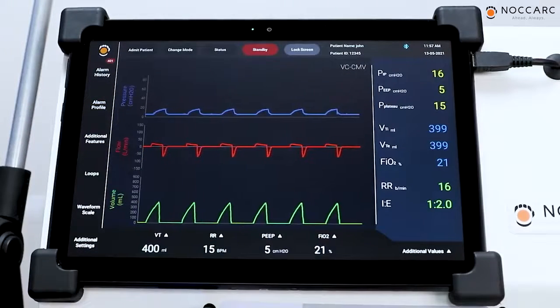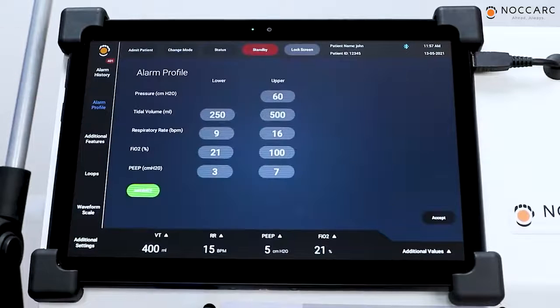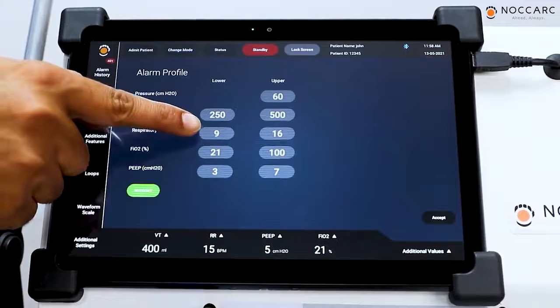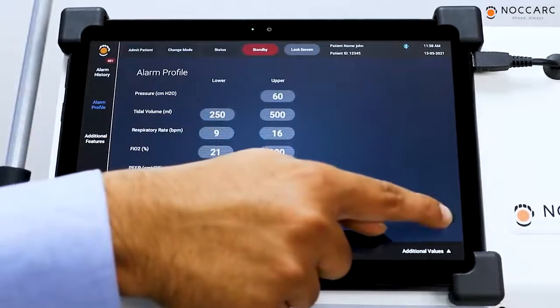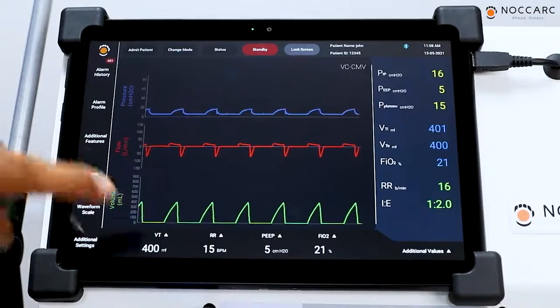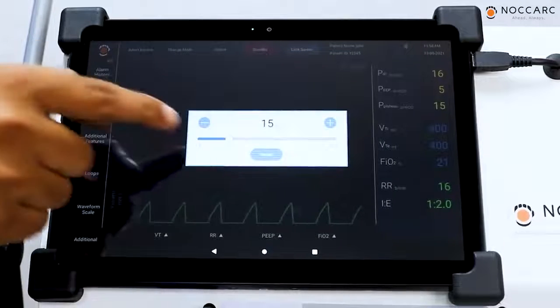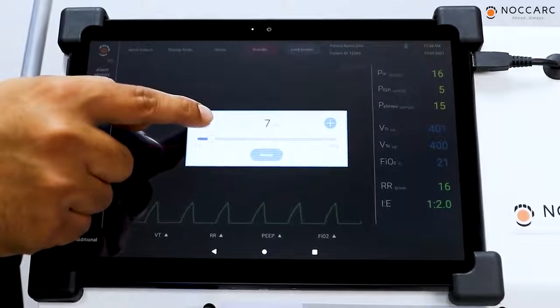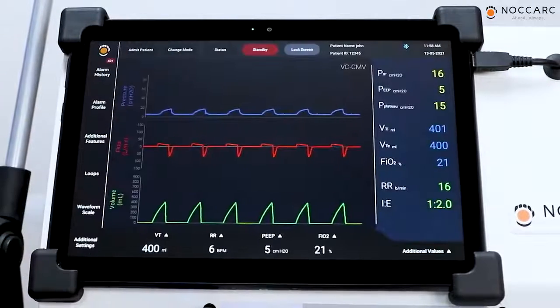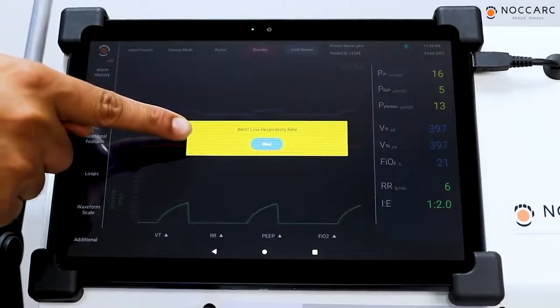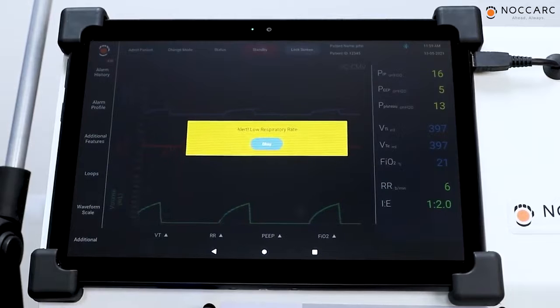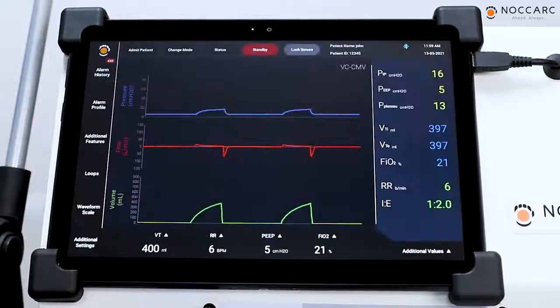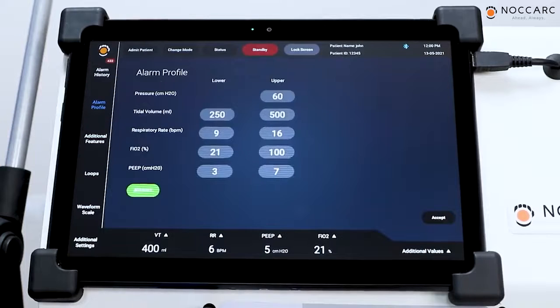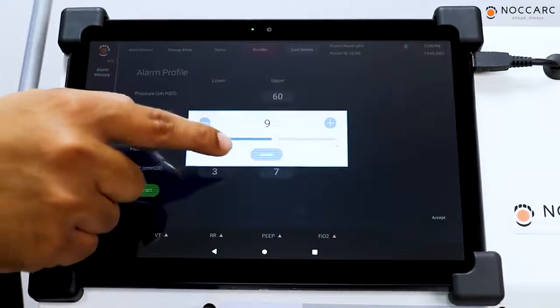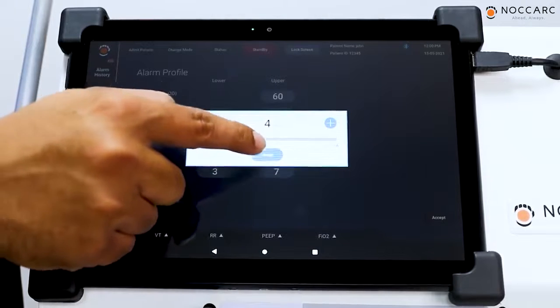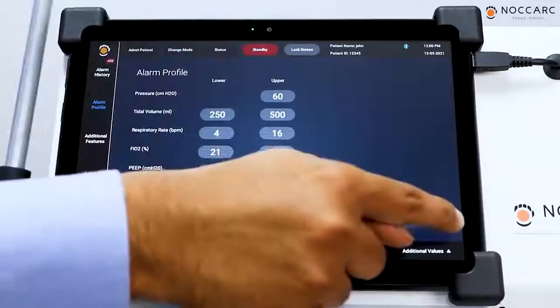To test the low respiratory rate alarm, press alarm profile. Here you can see the lower limit for respiratory rate is 9. Press accept. In the set parameters, press RR and set the RR less than 9. Then accept it. Here you can see a low respiratory rate alarm is showing on the screen. Press OK. Go in the alarm profile and set the lower limit for RR less than the set value and accept it. Press accept.